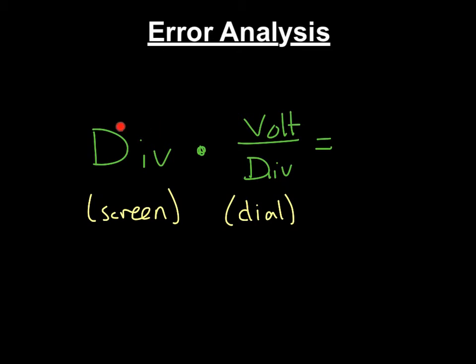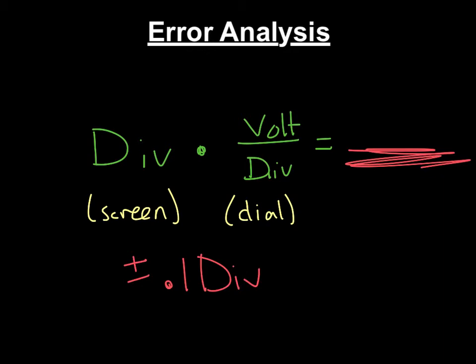Error analysis: you have divisions, which you read from your screen. You get volts per division, which you read from the dial. And then you get your answer, so some number right over here. Now let's say you have plus or minus 0.1 divisions, because you only trust yourself to read halfway between those divisions, which I think you can do better, but let's say you only do. So 0.1 divisions, and let's say you have 3 volts per division. Then your uncertainty goes to plus or minus 0.3 volts. And we get that just by multiplying these two together. So 3 volts per division times 0.1 divisions gives plus or minus 0.3. Not too bad. Not too bad at all.